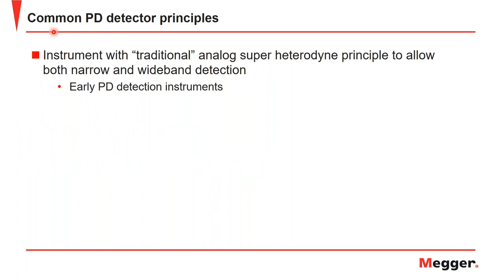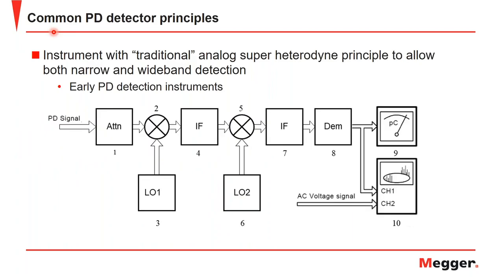Here we have a couple of common partial discharge detector principles, starting with the instrument with the traditional analog superheterodyne principle that allows both narrow and wideband detection. This is predominantly seen in earlier PD detection instruments, where you have your PD signal input coming into first the input attenuator, followed by a mixer with the first local oscillator fed into the first intermediate, with the second mixer and a second local oscillator fed into the second intermediate, and then finally fed into the demodulator, and then the meter and the oscilloscope for visualization of the partial discharge activity.